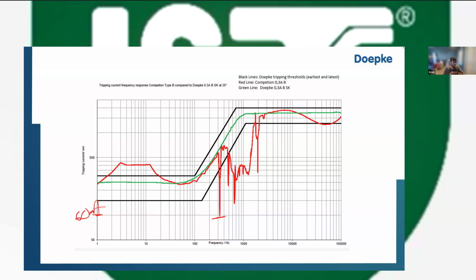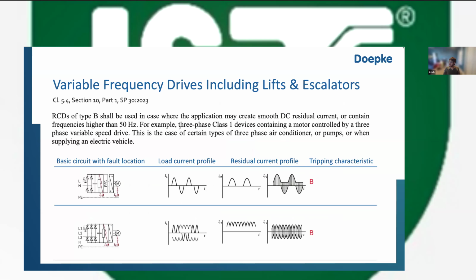So to answer your question, sir, 300 milliampere: is it right or is it wrong? Is it a correct practice? That depends on the application. But more importantly, is it the right type? It has to be type B because that is what NEC requires. If you go back to the slide on what NEC requires, it clearly mentions here that for three-phase class 1 devices containing a motor controlled by variable speed drive, RCD of type B shall be used. So this is what it is. I hope that answers that question.